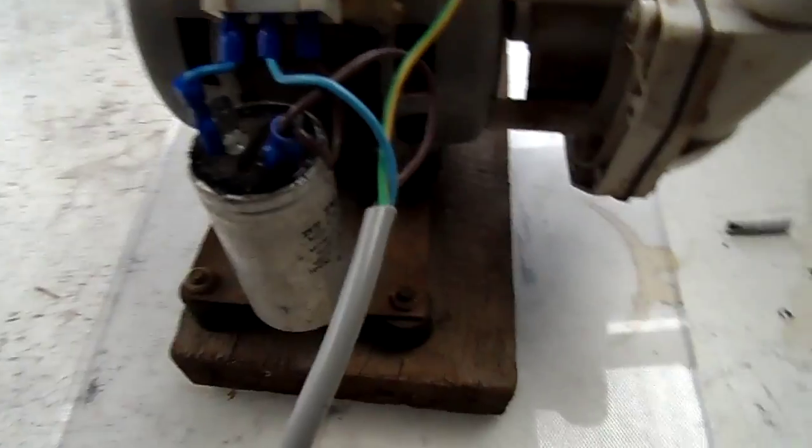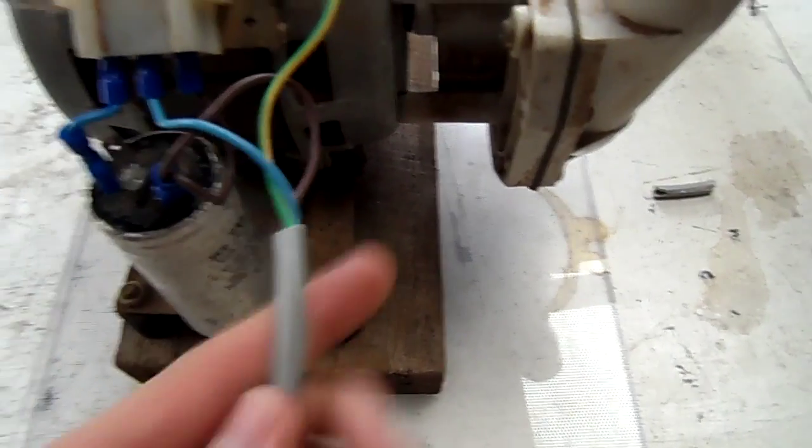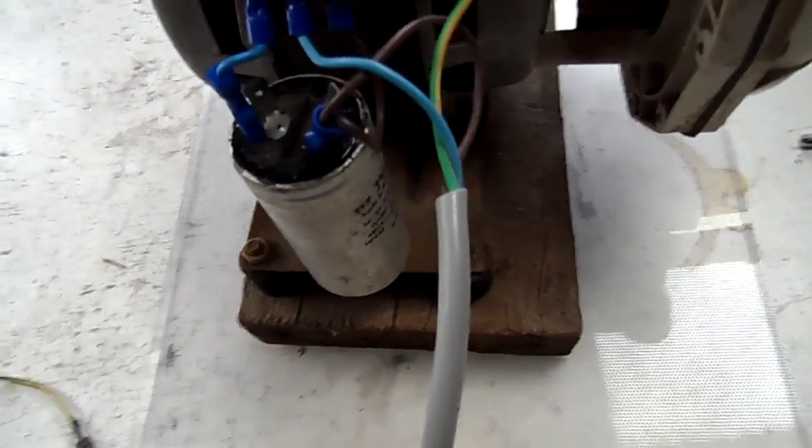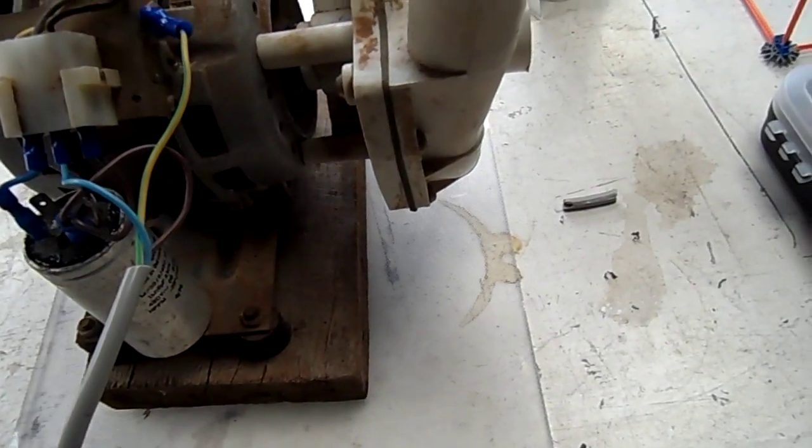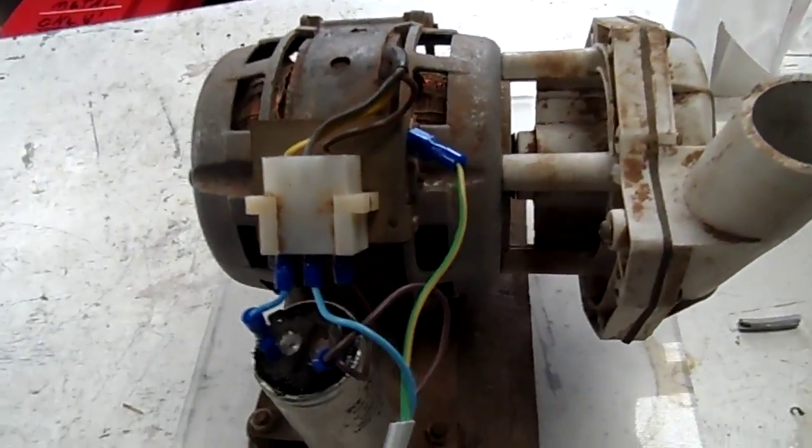The way to wire these up is your common goes to the middle. Your run goes to one of the terminals on the cap and then onto your active on the motor, and then the third one goes to the other side of the cap, which is the common for the cap start. But if you're running these on a variac, you don't need any of that. You just need the middle and the brown or red or whatever it is. Different motors vary.